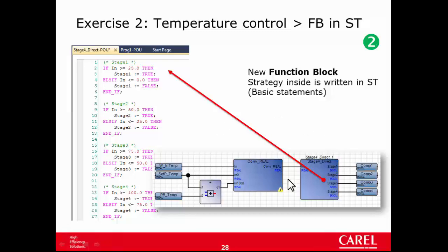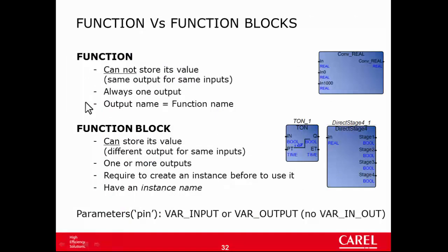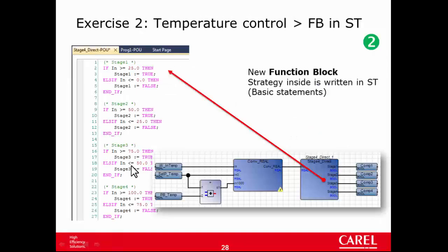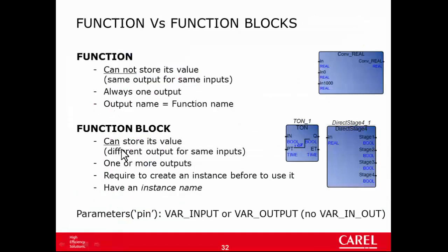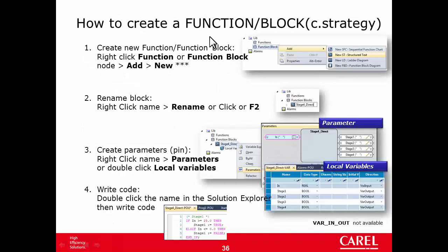Well, what kind of block do we have to use here? Function or function block? In this case, there is no choice. We must use function block for two reasons. The first, the block has four outputs. Second reason, the block has to save the status of four stages that depend on the previous value of the input and the previous value of stage. And only function block can have two or more outputs and then can save the previous values of the variable. So, we must use function block.